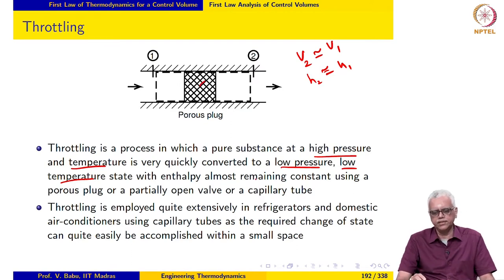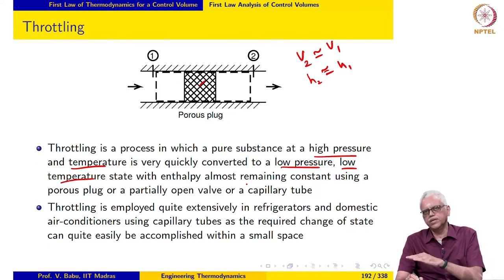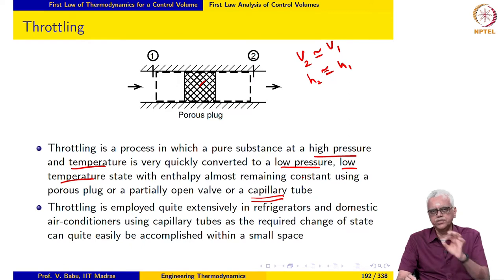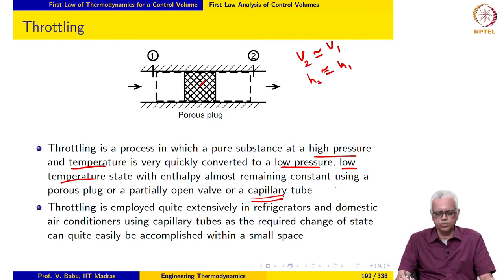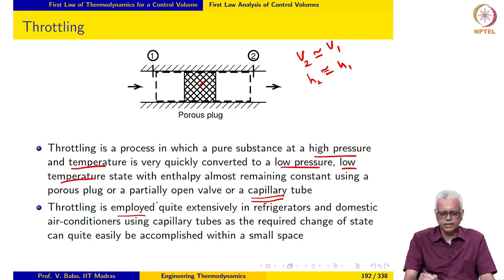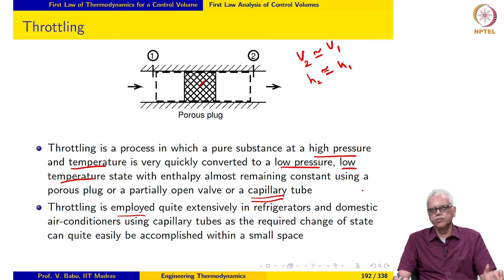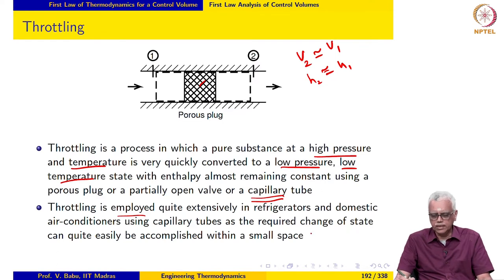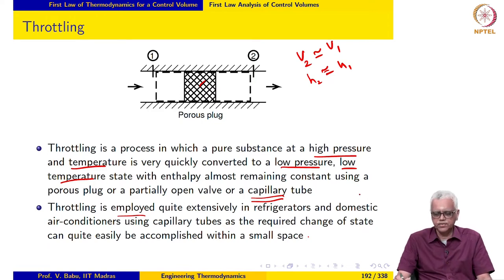Throttling is normally accomplished by making the fluid go through a very tortuous passage, such as a porous plug, or alternatively a valve that is partially open — causing a steep reduction in pressure and temperature. In practical applications, a capillary tube — a long tube of required length but very small diameter — may also be used. Throttling is quite extensively employed in refrigerators and domestic air conditioners. Capillary tubes are especially good: porous plugs may get clogged over time, but capillary tubes are easier to replace and service, so they are quite extensively used in domestic refrigerators and air conditioners.